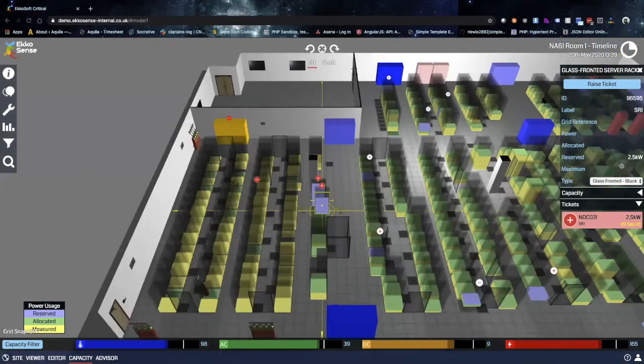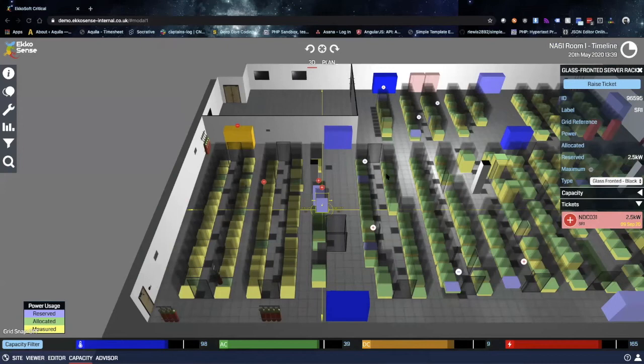So what you can do is go ahead and add it, raise the ticket and allocate some power to it. For example, 2.5 kilowatts for this rack. But then we can actually drag this rack around to different points in the room to see really where we could place it. Even though there's some open space up here, you can see it's being rejected either because it doesn't have enough cooling capacity or enough power on the side of the room to handle it. Then all you have to do is let it go, and it will go back to the original spot where it was if it can be accepted there. So that's really useful for simulating adding or removing equipment in a room without actually making any changes.